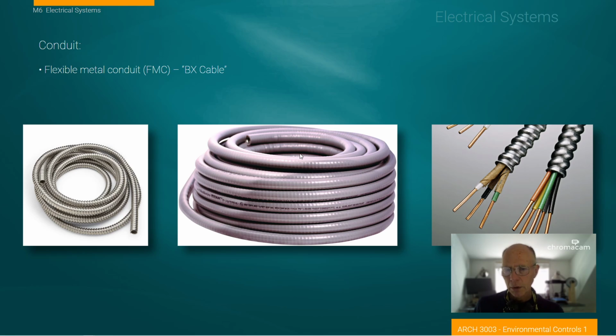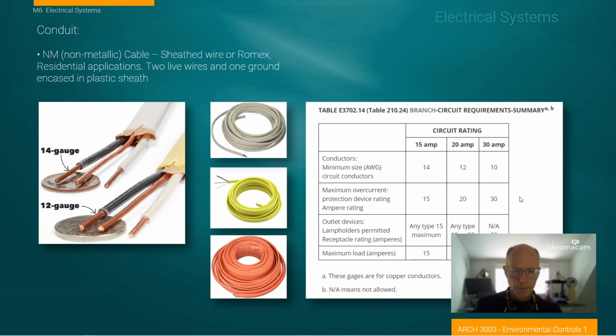Rigid conduit also has another form called flexible conduit. So we now can snake this through other more convoluted forms, or have it flexible as it branches off to supply something like an air conditioner. So we have flexible conduit. We have what's called liquid-tight conduit that's covered with a coating that protects against water intrusion for applications where it may be exposed to water. And then the final cladding or conduit system we have is called BX cable. And this sometimes is required in commercial installations, just a code requirement for a more durable cladding around the electrical conductors.